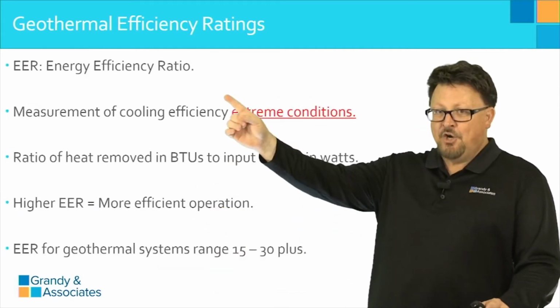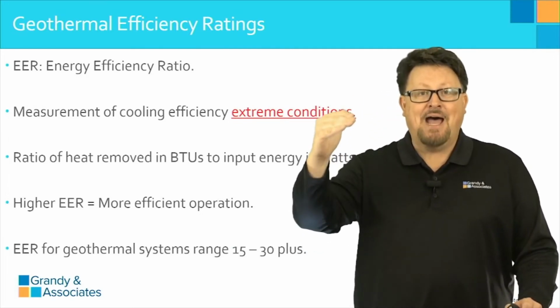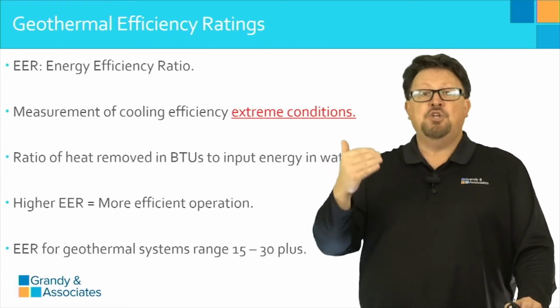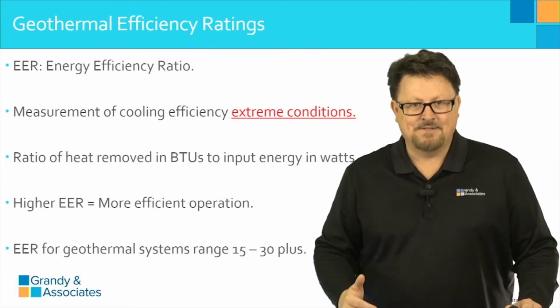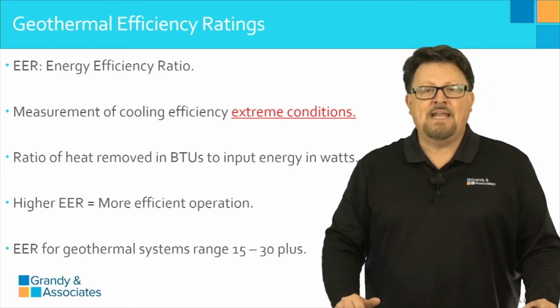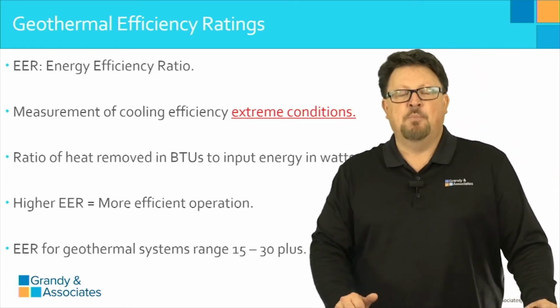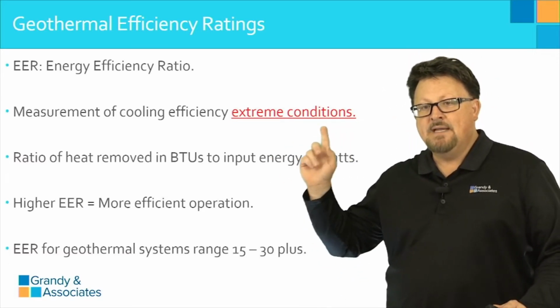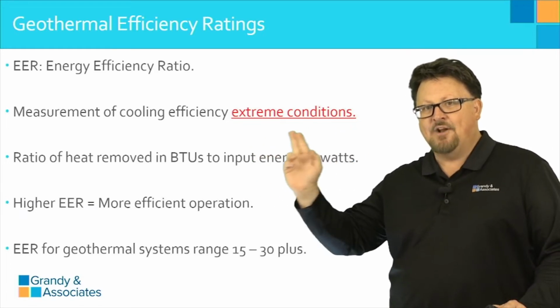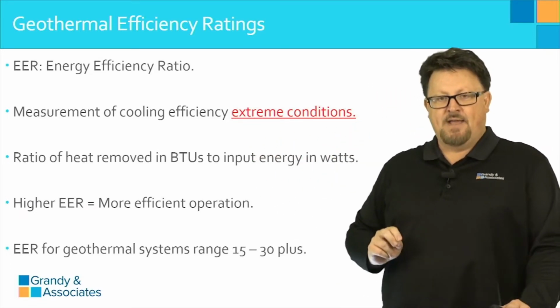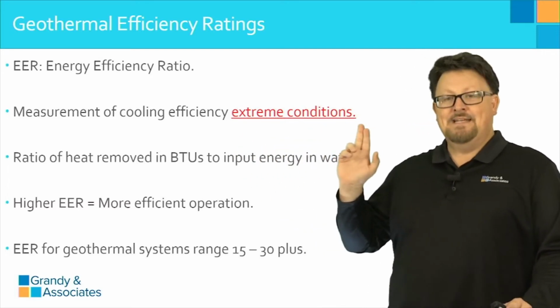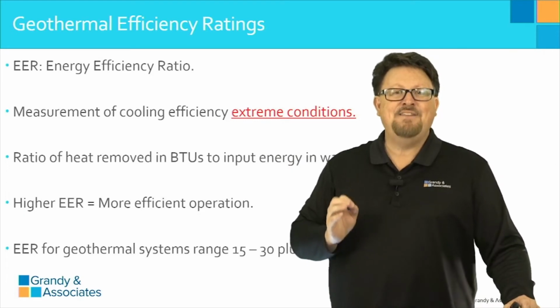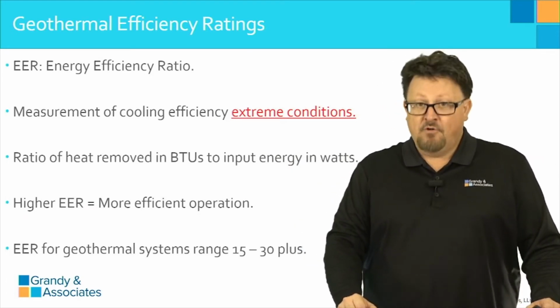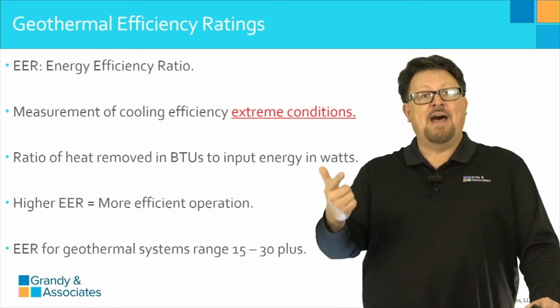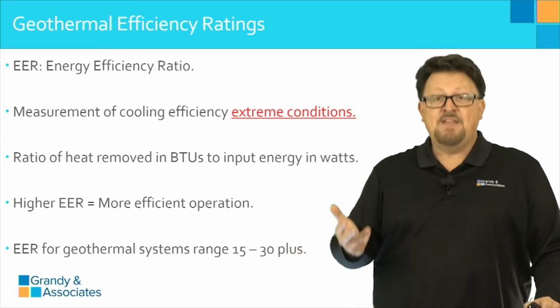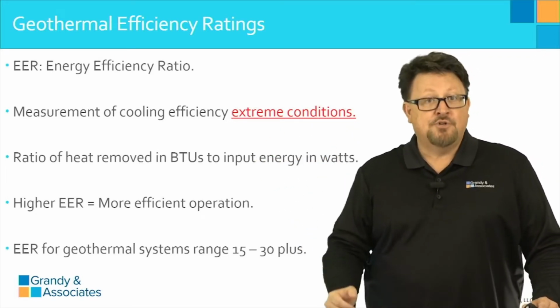However, here is where geothermal really shines, especially in some markets where you have long, hot cooling seasons. EER stands for Energy Efficiency Ratio. It is the measurement of cooling efficiency in extreme conditions. That is super important to highlight or underline, or something that's going to draw your attention to that. The definition of extreme conditions in this test parameter is a 95-degree outdoor temperature. Now, for most of the country, with the exception of California, Nevada, Arizona, and New Mexico, a 95-degree day is an extreme temperature day for sure.